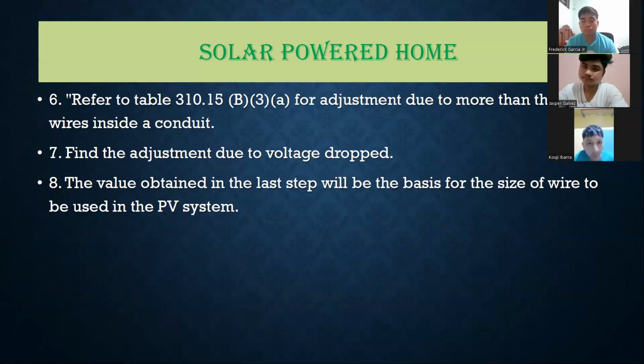So the next step was refer to the table 310.15(B)(3)(a), for adjustment due to more than 3 wires inside the conduit. So moving to the next step, find the adjustment due to voltage drop. After that, the value obtained in the last step will be the basis for the size of wire to be used in the PV system.